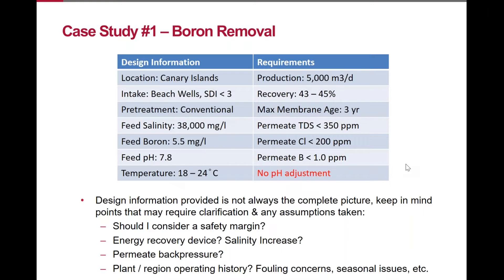Also consider if there's any permeate back pressure — this is important when sizing the maximum feed pressure for your pump. If you neglect to account for permeate back pressure, your pump sizing may be insufficient. Another thing to look into is the plant or regional operating history. If the plant has a history of fouling concerns, you may want to make the redesign more conservative — for example, with a lower system flux or 400 square foot membranes to reduce fouling.